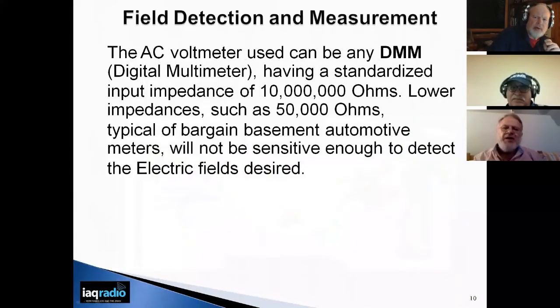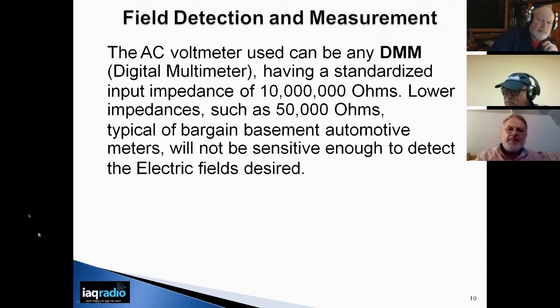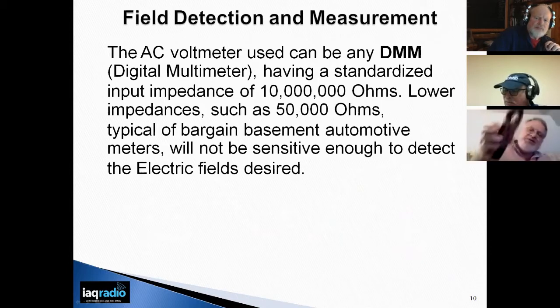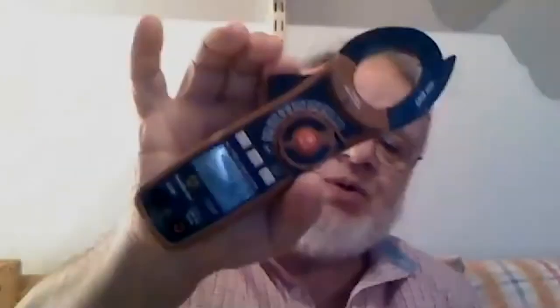We're talking about the AC voltmeter, which can be any digital multimeter having a standard impedance. The digital multimeter can take on any shape. I use this one partly because it's convenient and has a jaw for measuring current, in addition to being usable for measuring voltage and other things. But I could use a device as simple as this one, which may only cost $30 at a hardware store. If I want to measure current with this one, which doesn't have the jaw, I have to get a separate current attachment to feed into the two holes on the bottom of the unit. So some meters are a combination, and some are not.